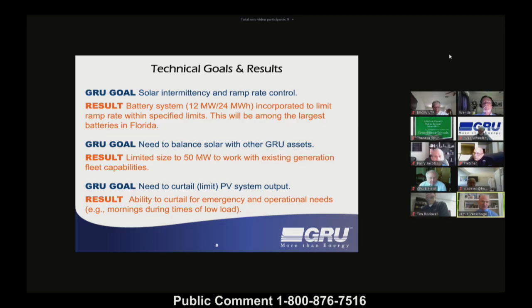GRU also needed the ability to curtail, meaning to not accept all or part of the system output at times. A good example is in spring and fall mornings, when GRU's customer load is near its minimum for the year. During these times, GRU's traditional generation units are sitting at the lowest level they can generate without tripping offline, and between about 8 and 10 a.m., the sun comes up and solar output ramps up quickly. GRU must match demand from customers with supply from generators at all times. If traditional units are already as low as they can go and a lot of solar comes onto the system, GRU ends up overproducing and pushing energy onto its neighbors, which can't be done for very long.